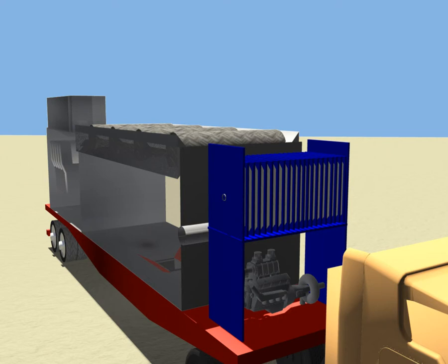The filter press is a plate and frame filtration unit that dewaters the sludge to form two streams, a sludge cake for waste disposal and a clarifying stream to be sent to the MVR units. As the sludge is passed through the unit, the filter frames become saturated with solid waste. These are scraped off during maintenance phases to produce the sludge cake, while brine water passes through the filters for further processing.